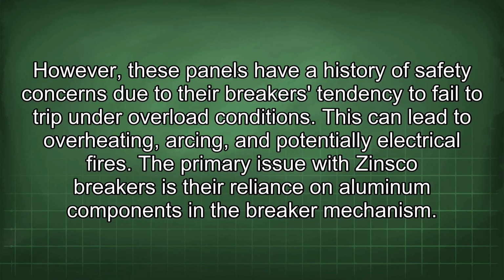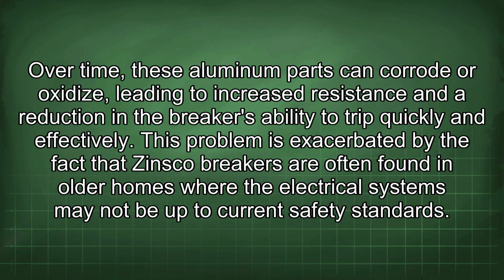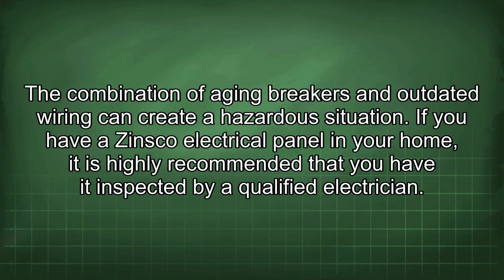The primary issue with Zinsco breakers is their reliance on aluminum components in the breaker mechanism. Over time, these aluminum parts can corrode or oxidize, leading to increased resistance and a reduction in the breaker's ability to trip quickly and effectively. This problem is exacerbated by the fact that Zinsco breakers are often found in older homes where the electrical systems may not be up to current safety standards. The combination of aging breakers and outdated wiring can create a hazardous situation.